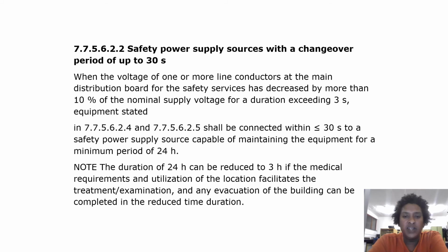Note, the duration of 24 hours can be reduced to 3 hours if the medical requirements and utilization of the location facilitates the treatment or examination, and any evacuation of the building can be completed in the reduced time duration.